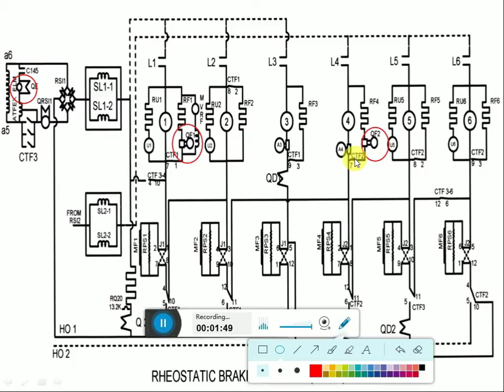The second type of current relay: QD1 and QD2, differential current relays. QD1 is connected between traction motors 2 and 3, and QD2 is connected between traction motors 4 and 5. If the difference of current between traction motors 2 and 3 or 4 and 5 exceeds 160 amps for goods locos WG5, WG7, this QD1 or QD2 will energize. Three actions will take place: auto regression, auto sanding, and LSP lamp. In coaching locos WM4, WP4, if the difference of current exceeds 125 amps, these QD actions will take place.